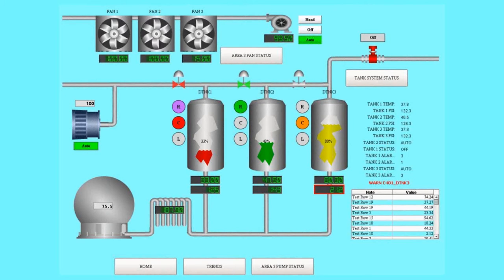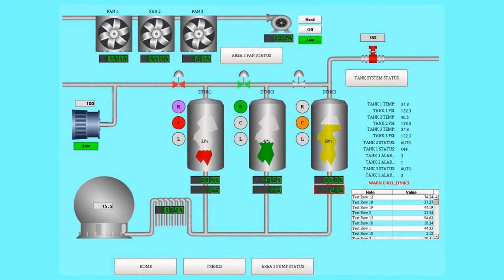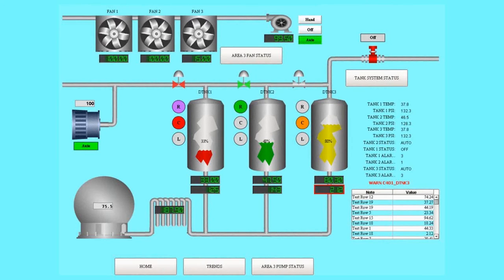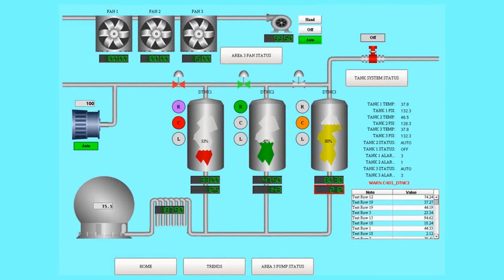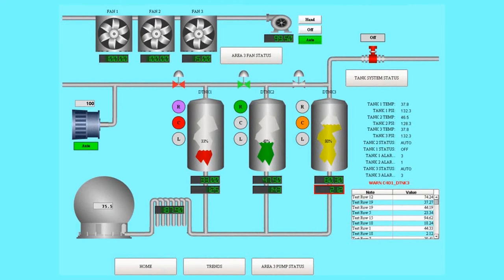Going back to our example HMI, we can see that there are some issues with visual clutter. There's a distracting animation that doesn't really provide a whole lot of information in return. In this scenario, we have some extraneous elements that aren't critical to this view, so maybe we can save them for a different view. There are also some distracting graphic choices, like the cutaway effect on the tanks, the way the equipment is drawn, and the gradient effect on the pipes.